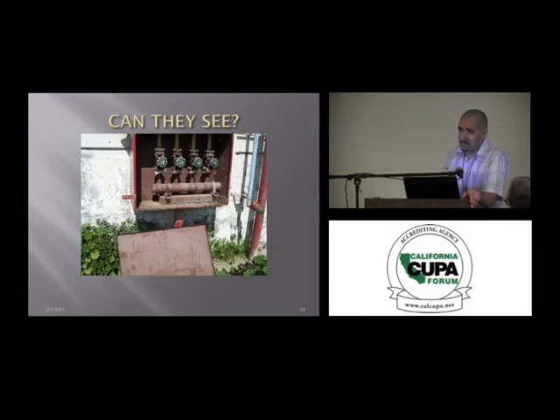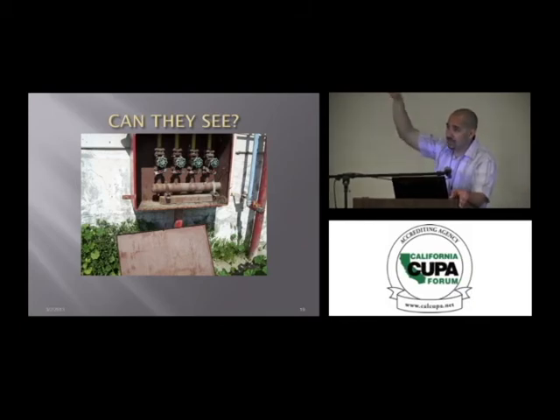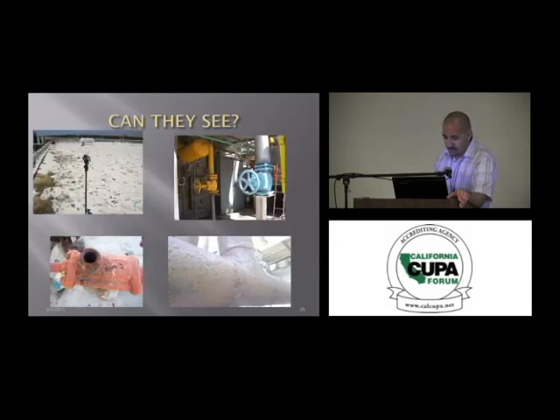And what happened at this facility, I'll mention real quick, mine did mention harmonic waves off the compressors. What happened was a compressor, the weight of the suction line was coming down, and it broke the bolts. The weight of the building came down, causing the bolts to break, causing a large ammonia release. Over 8,000 pounds of ammonia was released. And after that incident, there was absolutely no compliance going on with that facility, so they were terminated.